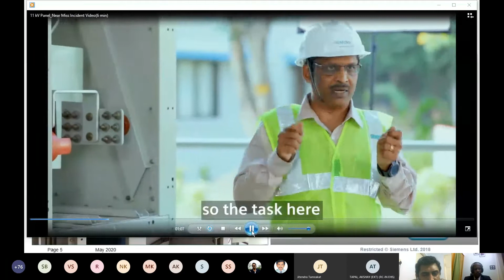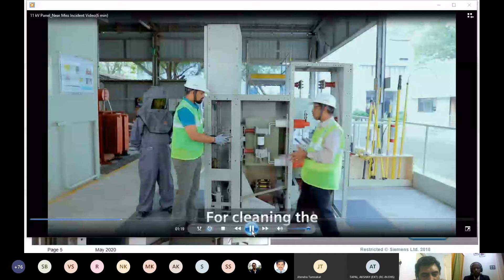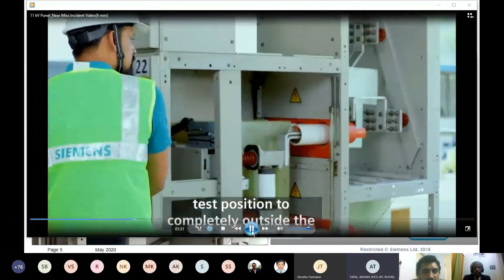The task here is to clean the circuit breaker compartment. For cleaning the circuit breaker compartment when the breaker is in service, we have to remove the breaker from service position to test position, and then remove it from test position to completely outside, because somebody has to go inside and clean the compartment.